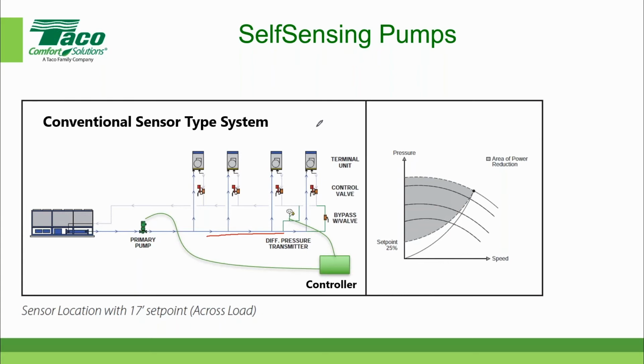I'm sure it did. Here's another great question that I know you like to answer. Can the differential pressure transmitter be located near the pump? And the answer is no, because if you locate it near the pump, then you're only measuring the pressure differential across the pump. You're not taking into consideration the increase or decrease in pressure differential of the system as the load changes. And if you measure it across the pump, for all practical purposes, you turn the pump into a constant flow device or constant speed device. So you need to measure it at the most remote point.